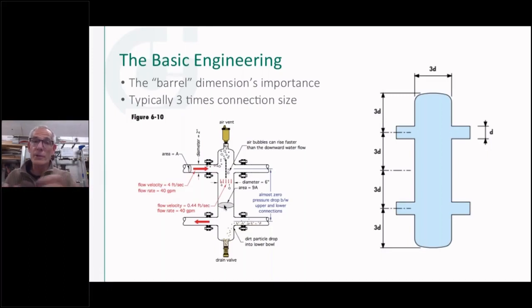And if you do that 3-to-1 relationship, that's going to assure that you have enough space in there, so to speak, that we're going to have a very low flow velocity from the top to the bottom of that with 40 gallons a minute going through here. I've got less than a half a foot per second velocity. So I've got very little movement from the top to the bottom here when I'm flowing that kind of rate, because I've just increased the size of that chamber by 3 times. I went to a 6-inch pipe with 40 gallons a minute going through it. That's where I get my velocity drop.